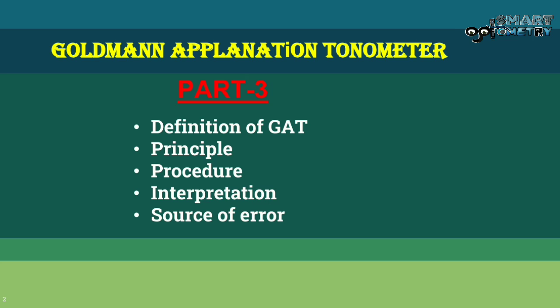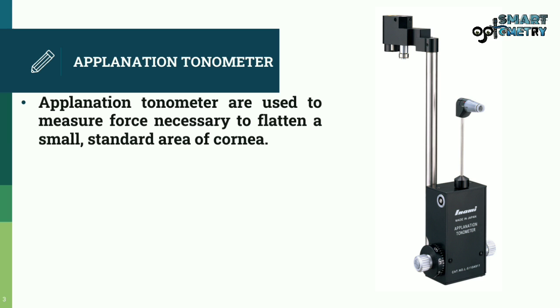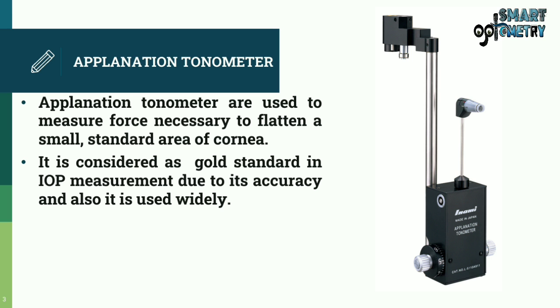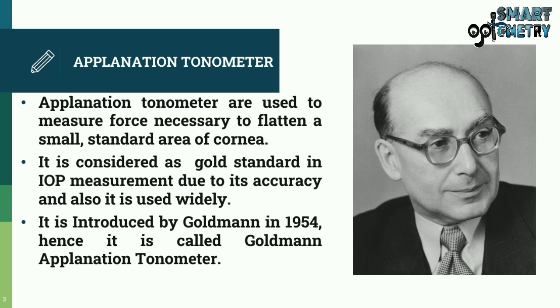Applanation tonometers are used to measure the force necessary to flatten a small standard area of the cornea. It is considered the gold standard of IOP measurement due to its accuracy and wide use. It was introduced by Goldmann in 1954, hence it is called the Goldmann Applanation Tonometer.